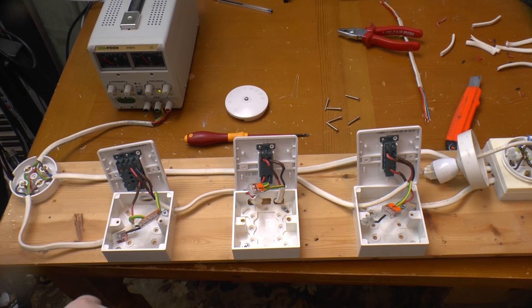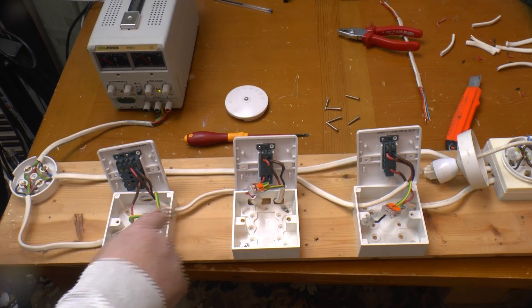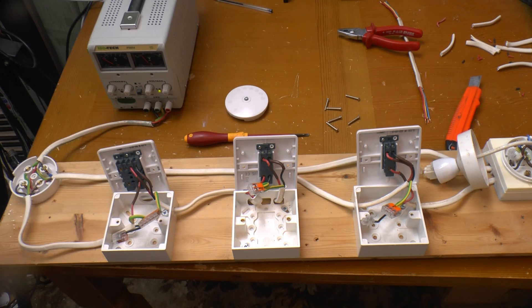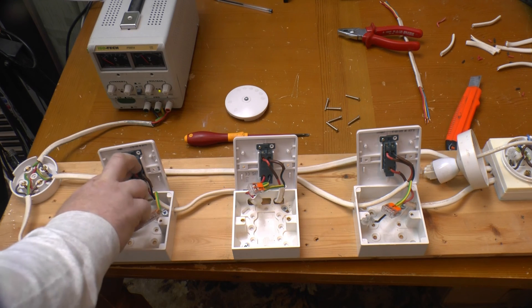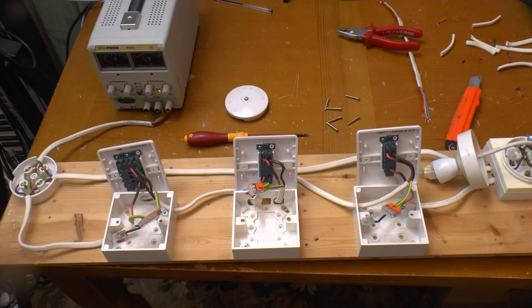The colour coding on the two two-way switches is like for like, unless, like I said, you want to change whether the light is on or off in the all switches up or all switches down position, in which case you swap a pair over.